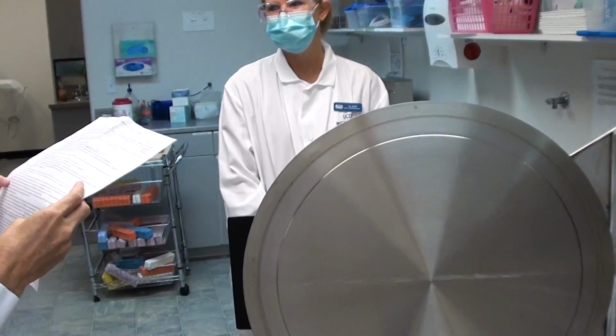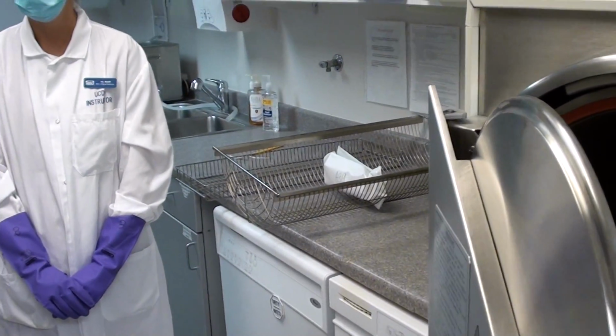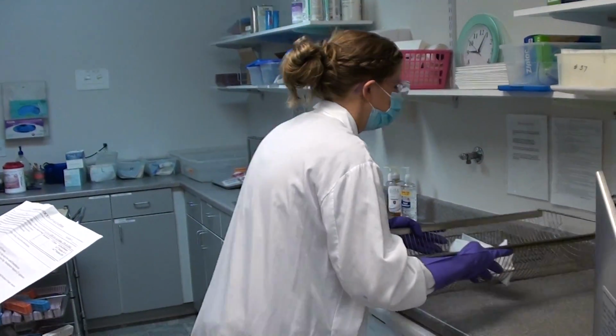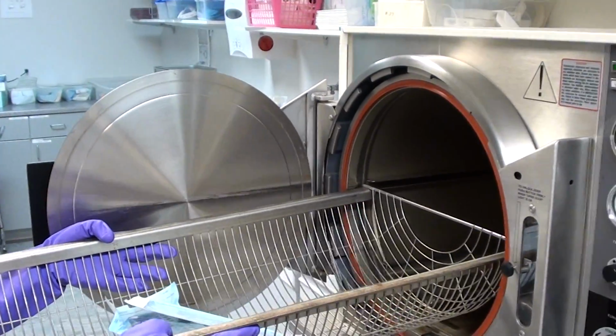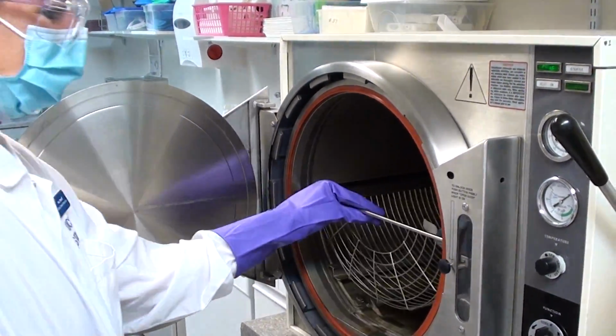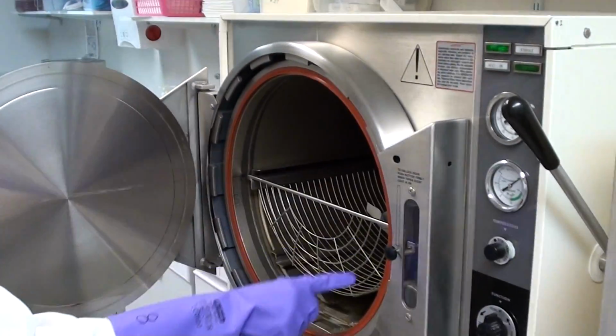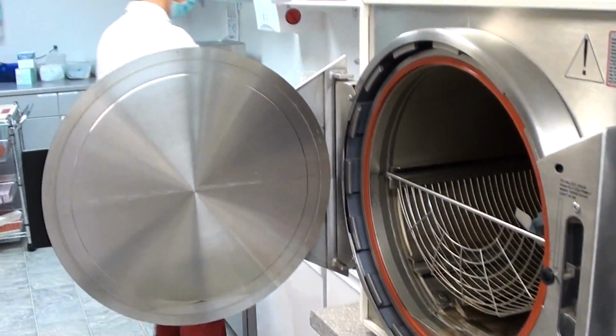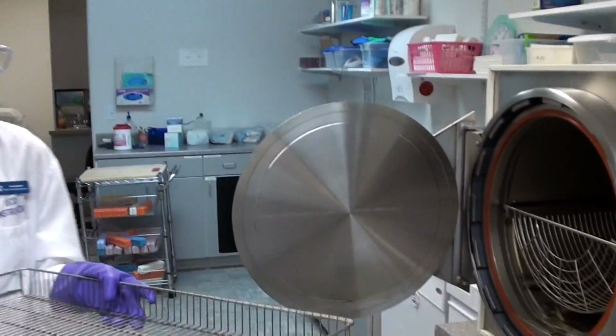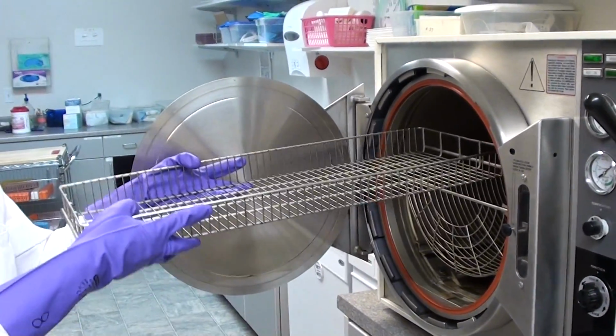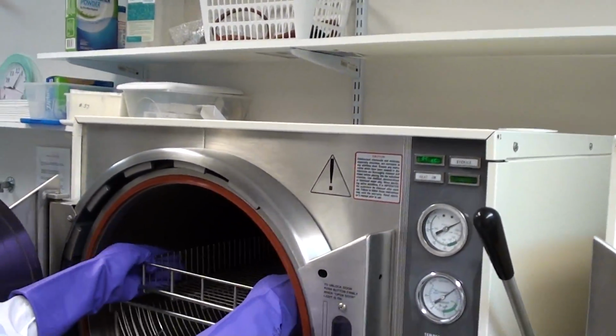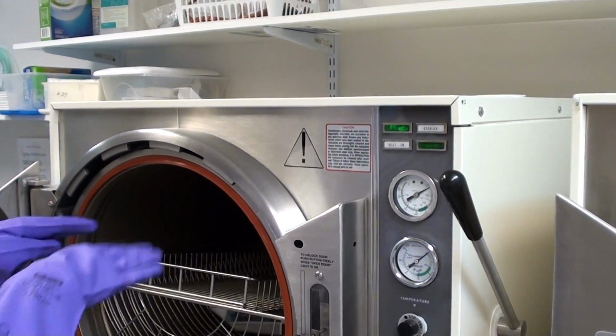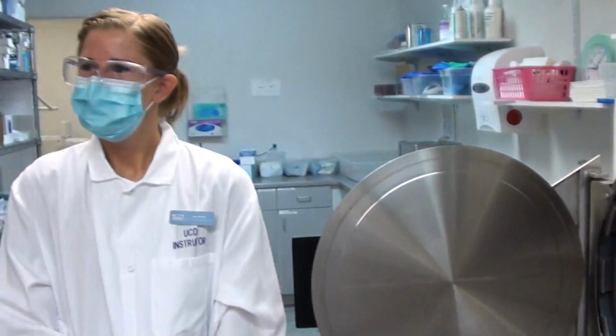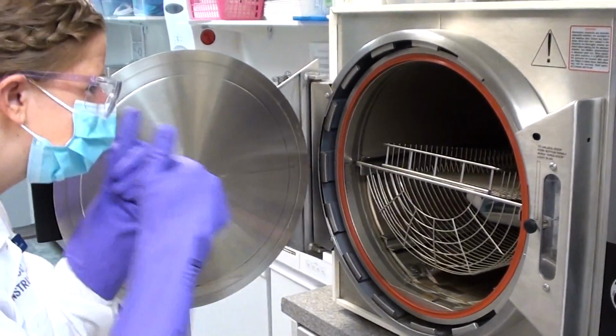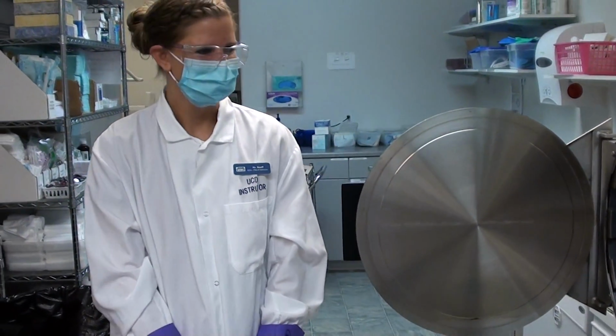Okay, what do we do next? Next, if starting a cycle immediately, we will load the instrument basket into the autoclave, avoiding any contact with the rubber gasket around the door, and use caution when placing the top basket on the bottom basket so that you don't tear any sterilization bags. This is the gasket that you're avoiding. Pretend this is full and it's heavy, but you don't want to just shove it because you'll tear everything. You kind of need to lift and then set it down on top. It will be level because there'll be stuff in it. She's going to check for any items that may be touching the sides of the autoclave or the rubber gasket, and she'll reposition bags if necessary.